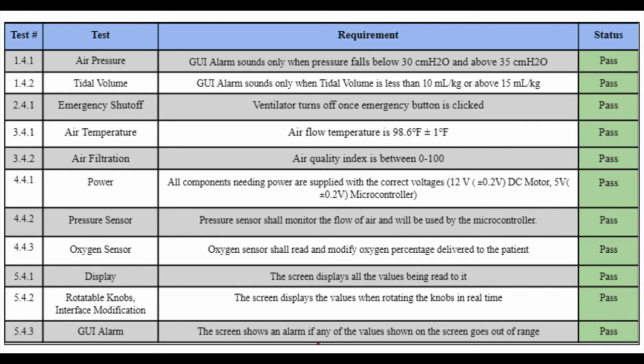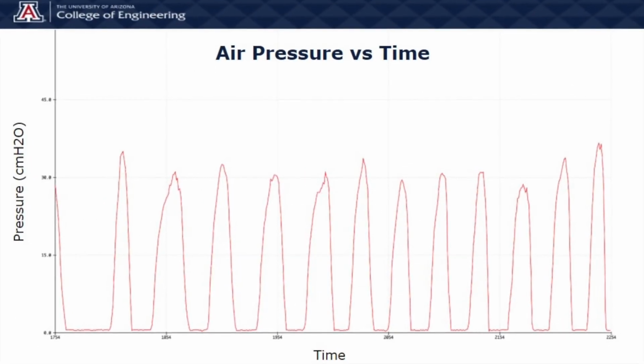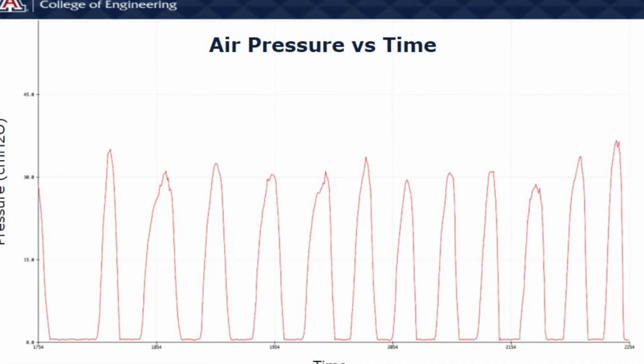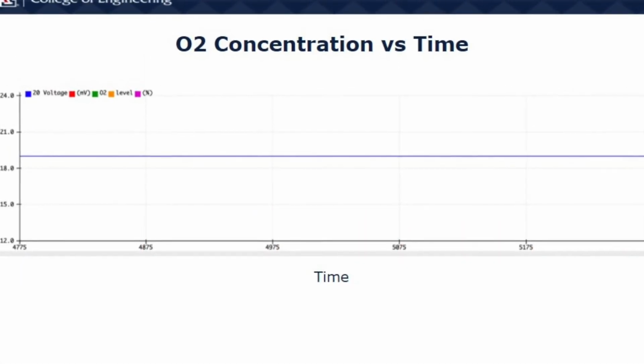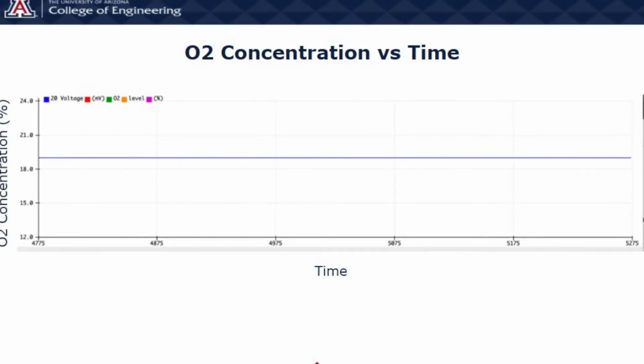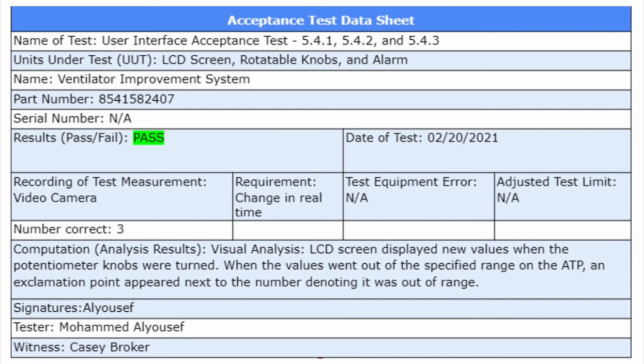For regulation, we tested to make sure that the temperature of the air being supplied was 98.6 plus or minus 1 degree Fahrenheit. We also tested the air quality index of the exhaled air to make sure that the decontamination chamber was filtering it properly. As discussed previously for the electrical ATPs, we tested the pressure and oxygen sensors. For the user interface ATP, we tested that the display, interface modification upon adjusting parameters using the rotatable knobs, and the GUI alarms were working. We recorded the results from each of our acceptance tests in datasheets like this one. The one displayed is for our user interface test.